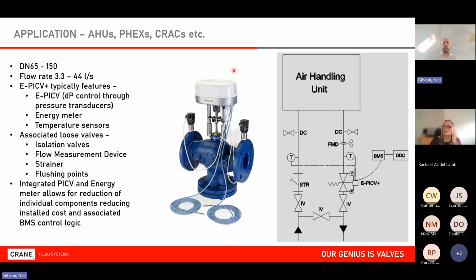So while this technology itself is generally a higher cost compared to a 0 to 10 volt actuator, say, the cost difference, once you take into account all of the other components you do not need now, if not cost neutral, will be a cost benefit. Plus, you get all of the operational benefits from the valve controlling based on temperature, based on power. So you get operational efficiencies.